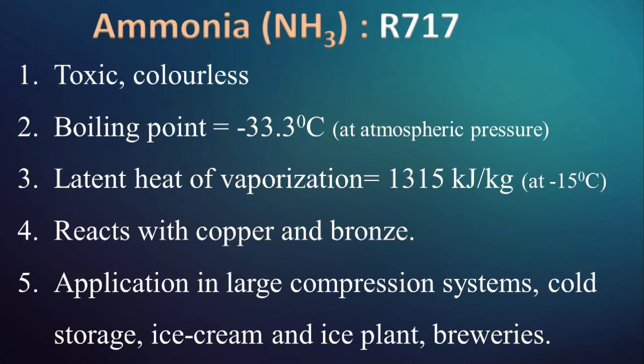Ammonia highly reacts with copper and bronze, so we generally use iron or steel in ammonia systems. We find applications of ammonia in large compression systems, cold storage, absorption systems, ice plants and breweries.